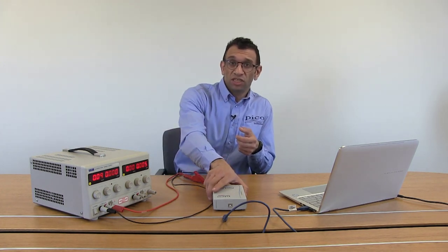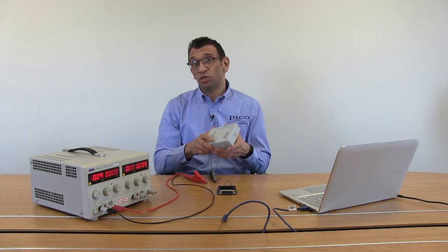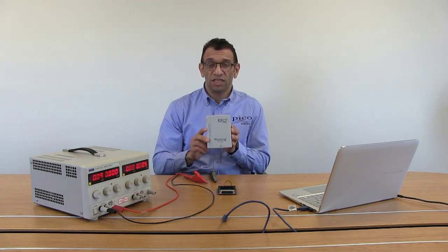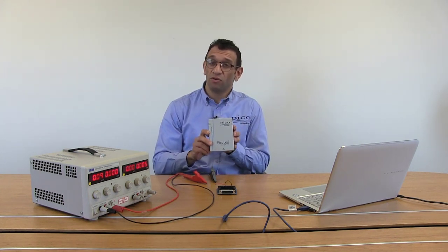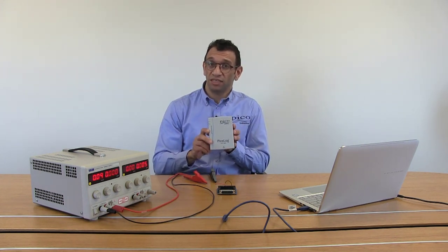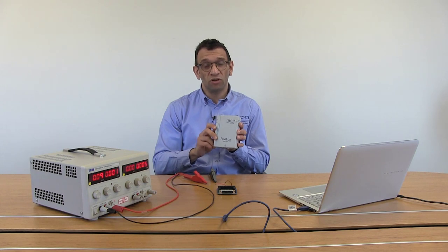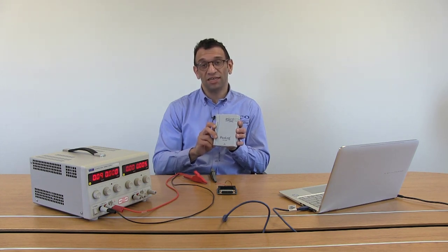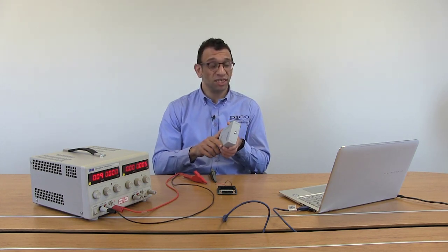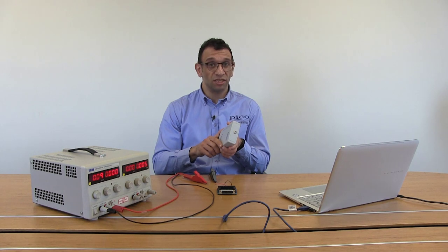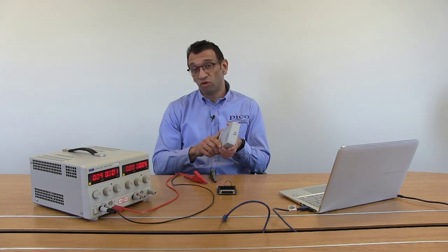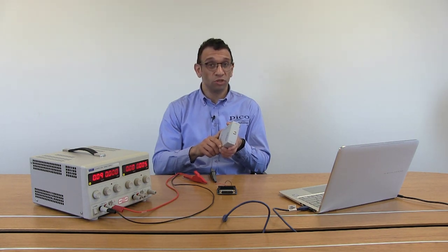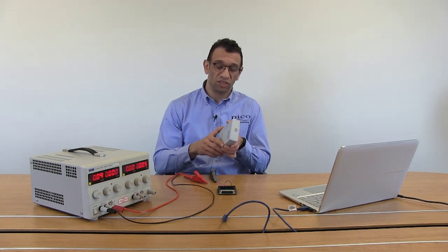To demonstrate custom scaling, we'll be using the PicoLog 1216 data logger. This is part of the PicoLog 1000 series of data loggers, which is a low-cost, high-speed multi-channel data logger that can take up to 16 channels, up to 12 bits resolution and can measure 0 to 2.5 volts.